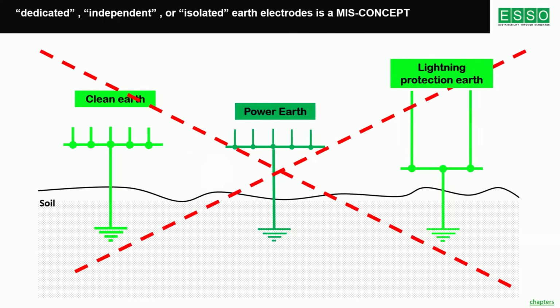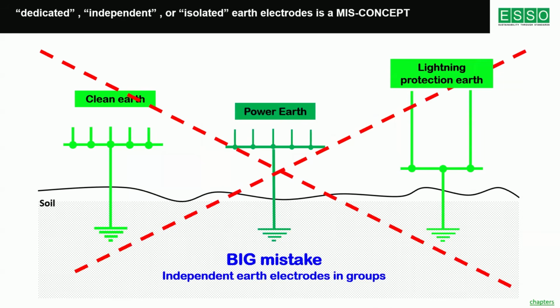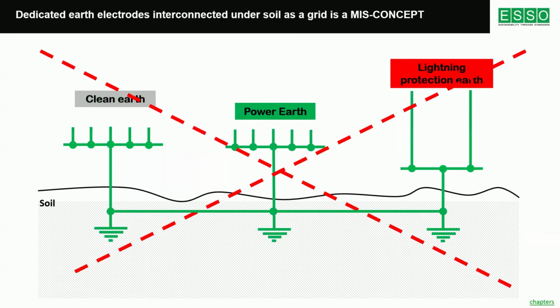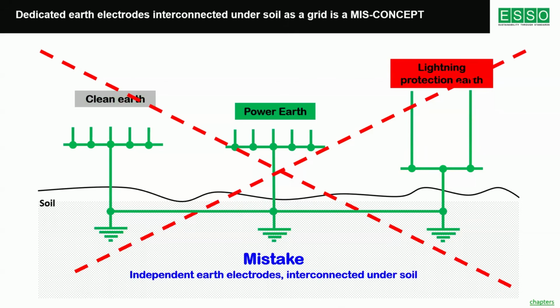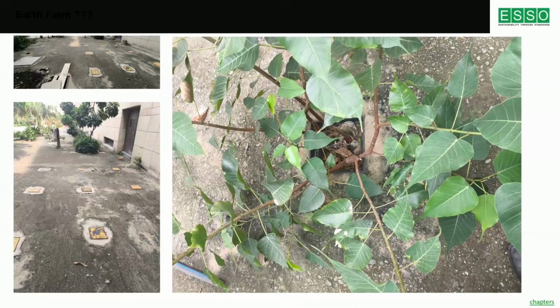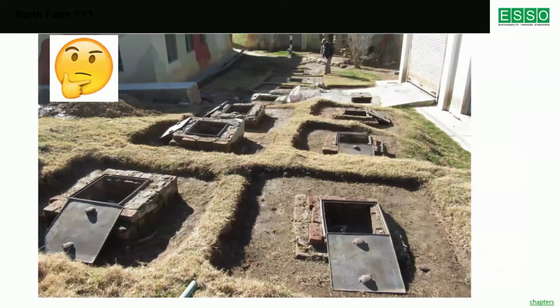Similarly, the concept of clean earth, power earth, lightning protection, separate earth. This is a big mistake. Also separate earthing and everything interconnected under the soil, and thinking that this will provide a safety is a big mistake. Earthing is not a subject which is talking about earth electrode. The term earth itself means you are making a connection to a local earth, not to the earth pit. Earthing and earth pit are two different subjects.